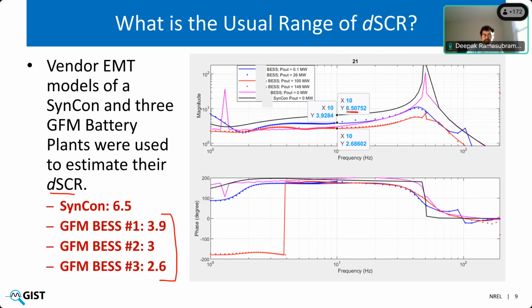But as Shahid said, if you hit a limit, if you go into a saturation, if you have a hysteresis inside your loop, or if you have a dead band in the controls, depending upon what type of resource one is operating, those elements will play a role in providing a different kind of response. For example, say the Q by V scan, if a resource has a dead band of, let's say, 0.05 PU in their voltage controller loop, and one is carrying out the scan at 1 per unit nominal voltage, the dead band will play a role where you wouldn't see a certain behavior. If you do the same scan with the same perturbation magnitude, but at, say, 0.95 or 0.94 per unit voltage, which is outside the dead band, one can get a different response in the scan.